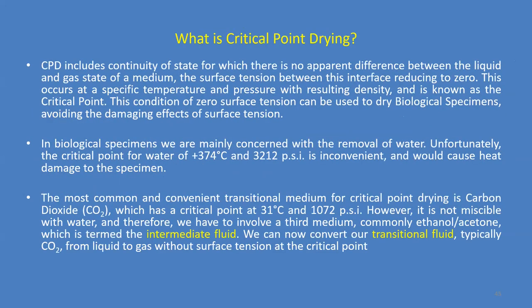So critical point drying is what happens when there is no apparent difference between the liquid and the gaseous state of the medium. The surface tension here is reduced to zero, and this occurs at a specific temperature and pressure with the resulting density known as the critical point. This condition of zero surface tension can be used to dry biological specimens or delicate specimens, and you can avoid the damaging effects of surface tension.